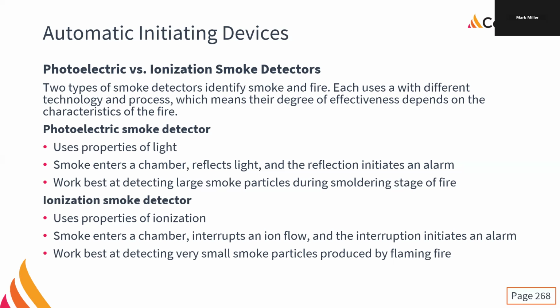We're using light. The smoke enters a chamber. There's a chamber inside, and the light gets reflected by the smoke, because it is an absolutely black, baffled chamber, so no light is being reflected. We put the smoke in, and it starts to reflect, and that reflection goes to the light sensor, and it initiates the alarm. They work best at detecting large smoke particles during the smoldering stage of the fire, which is the second stage of the fire, visible products of combustion, because we need enough smoke and large enough smoke particles that we can reflect light off of it easily.